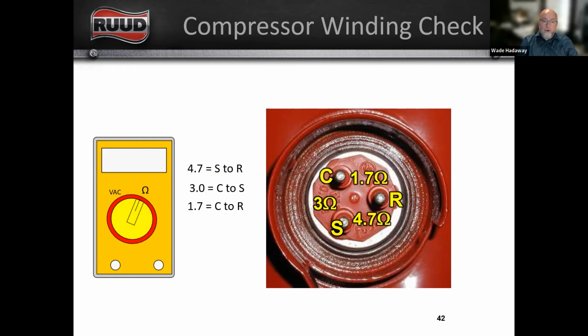You can do it where your compressor plug wires into your contactor and your capacitor, or on a 3-phase compressor, they're all going to measure out as the same ohms. But even on an inverter system, you don't have to pull the plug and get in there. The only time I would do that is if I did my compressor check and I didn't like the readings that I got. Let's say I got 1.7, 1.7, and 2. Well, I don't like that. So then I'm going to pull the plug and check at those terminals, because I could have an issue with the wiring in my plug or in my compressor harness.